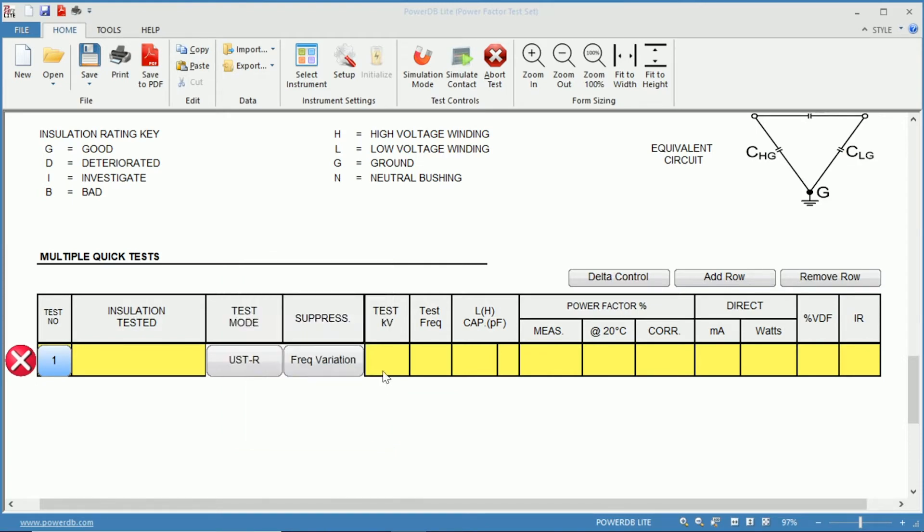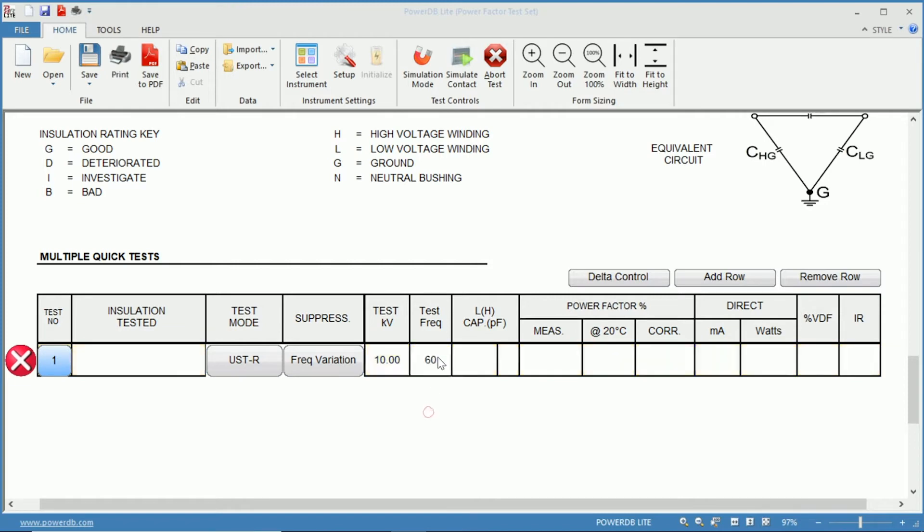You can choose the test voltage in kilovolts, as well as the test frequency, whether it's 60 Hz, 50 Hz, or some other frequency you wish to test at. Then you can get your power factor measured, as well as your milliamp and watts.